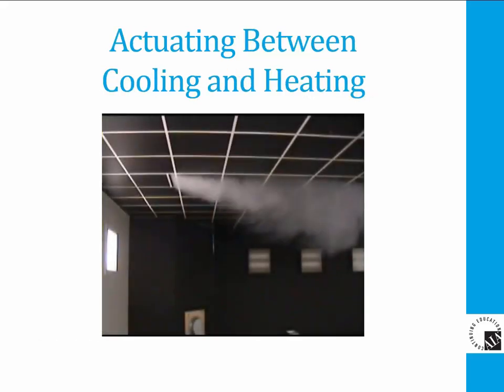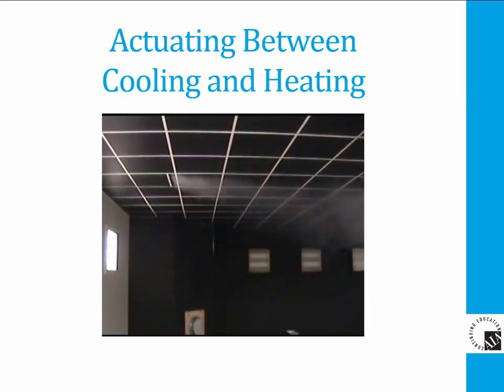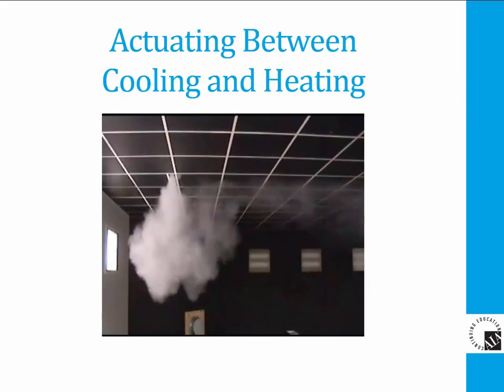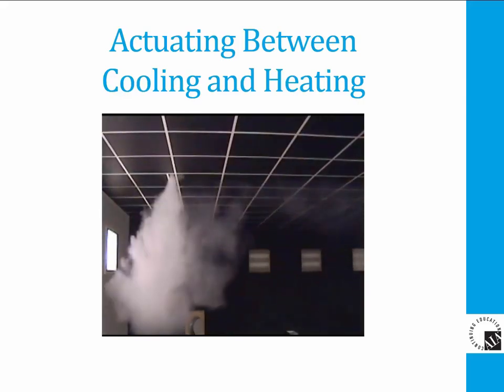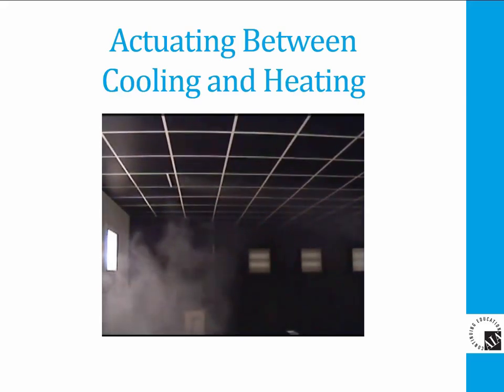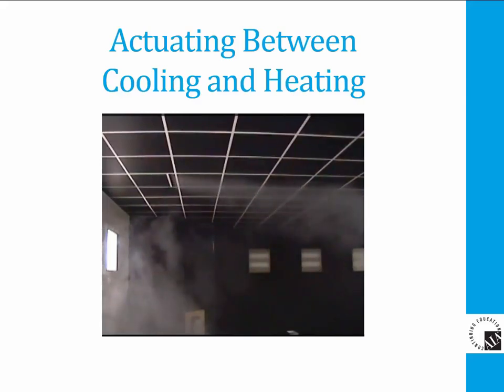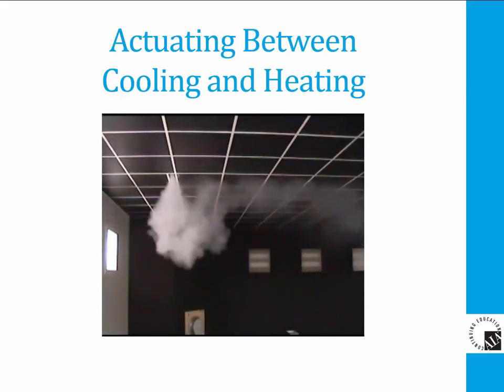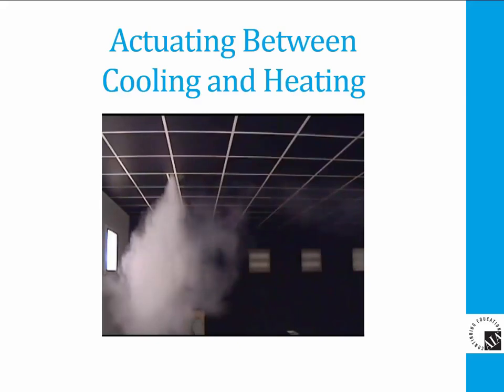This smoke video illustrates that when the supply air reaches the changeover temperature, the pattern switches instantly from horizontal cooling to vertical heating and then back on demand. The heating pattern is directed back at an angle of about 10 degrees so that the unit can be located 18 to 24 inches away from the glass, with the air directed toward the front edge of the glass.